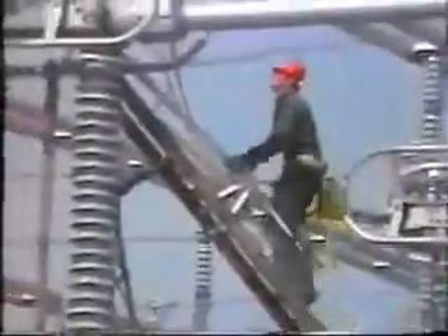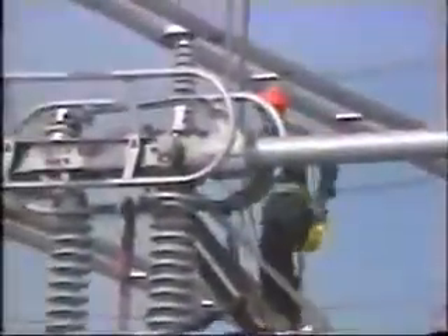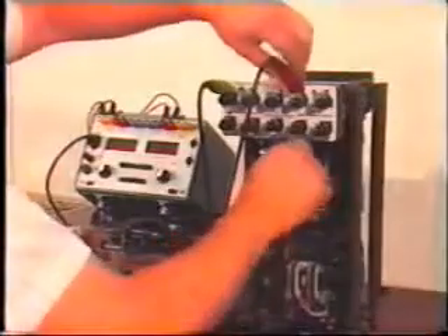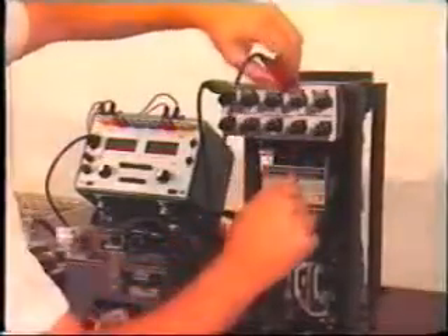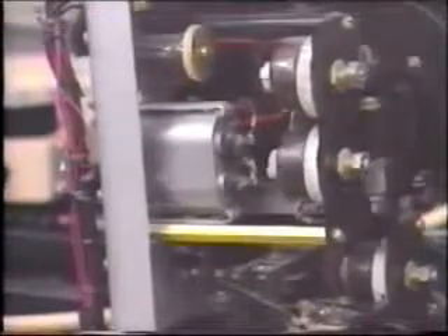So far, we've been looking at very general safety precautions that apply to most work activities around the switchyard. However, there are also a number of specific hazards that very much affect the relay technician. For example, many relays include a capacitor as part of their internal circuitry. Even if the relay is de-energized, the capacitor will hold its charge for some considerable time. If you happen to place yourself across the capacitor, you'll be in for a very nasty shock. Make sure to always short the capacitor terminals before touching it.